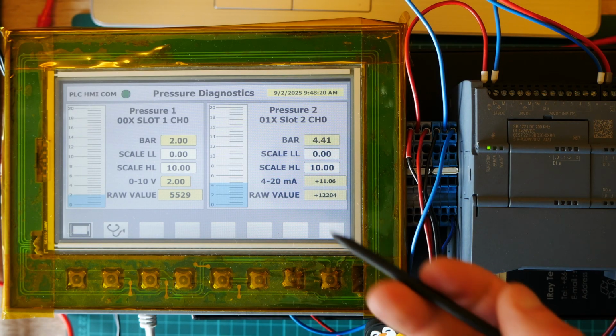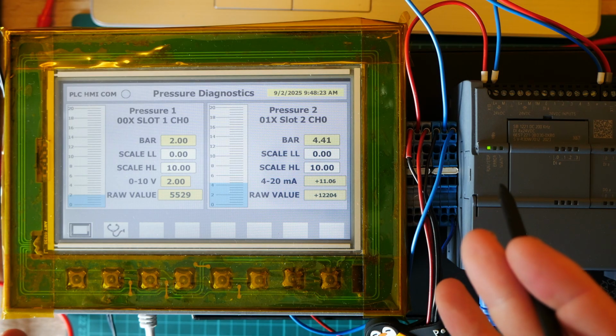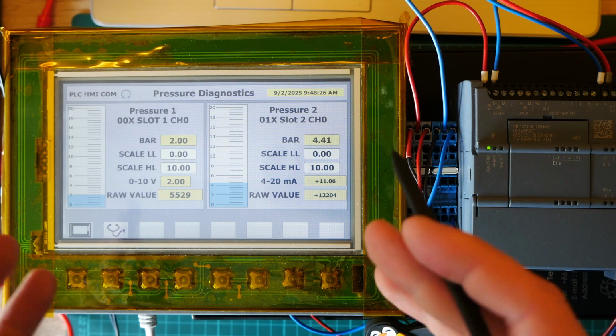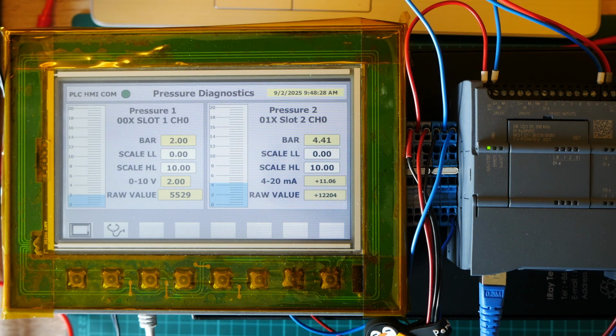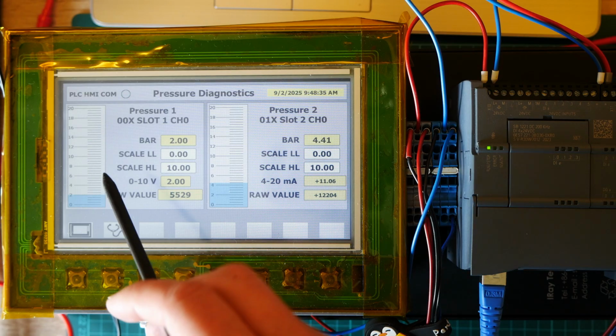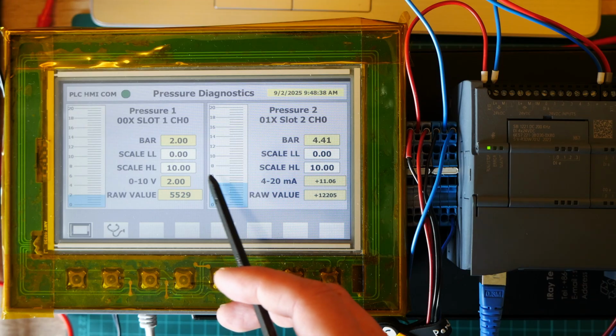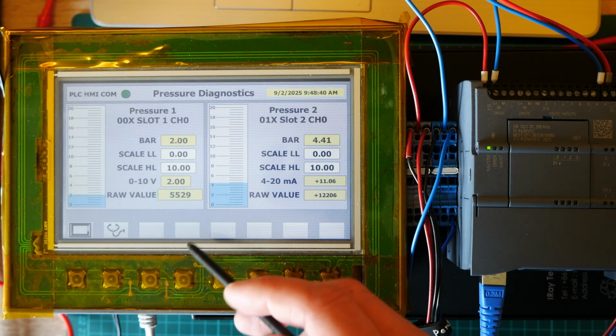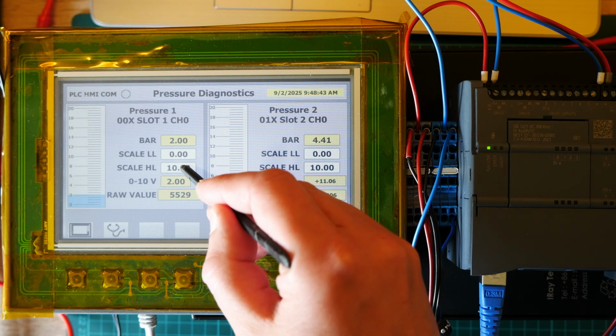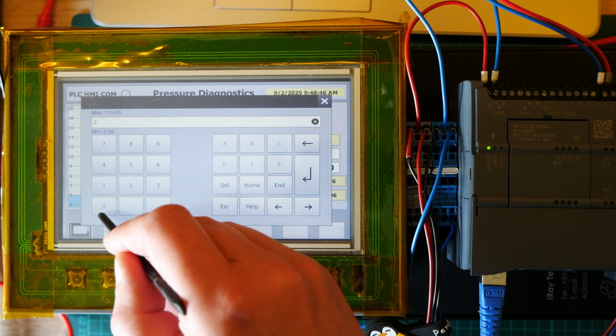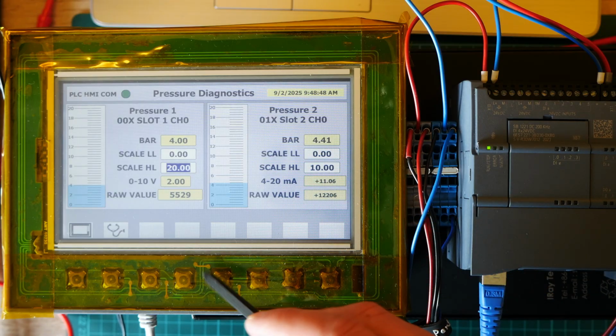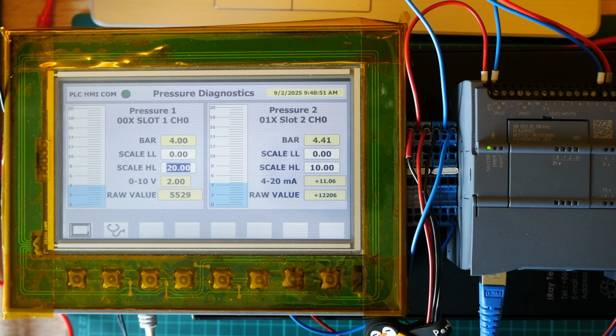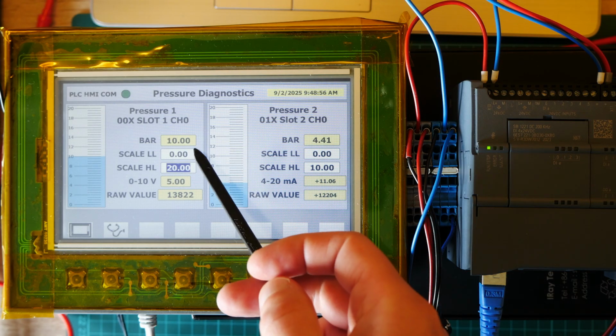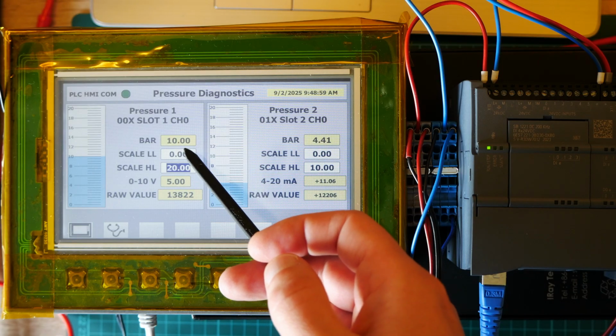And let's say you don't have at this moment a sensor from 0 to 10 bars, but you have a sensor from 0 to 20 bars. So this is why it's a very good idea to have these scales. Here you can just go and change the high limit of the scale. And right now we put, let's say, again 5 volts, and we see around 10 bars.